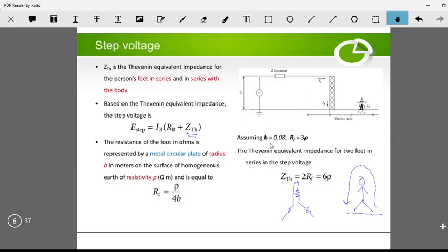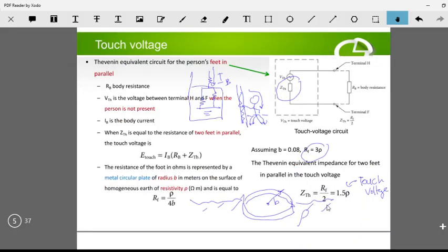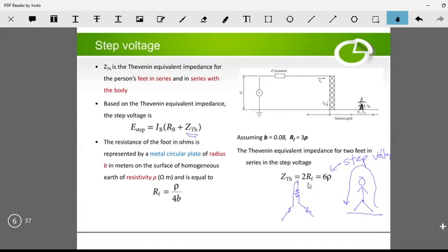Again, if we assume b is equal to 0.08 and R_F is equal to 3 rho for the typical case, we can define the Z_TH for the step voltage case as 2 times R_F, because these are now in series, so you get 6 times rho. Earlier, these were in parallel, so you had R_F by 2 R_Fs in parallel giving that value; here, 2 R_Fs are in series, so Z_TH equals 2 R_F, which is 6 times rho when R_F equals 3 times rho.